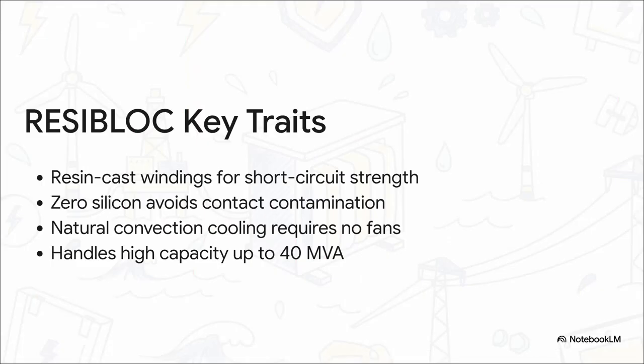Okay, let's pull all this together. Before this explainer, you might have just thought of a dry-type transformer as a generic category of equipment, but now you know the exact traits of a RESIBLOC specifically. You've got resin-cast windings for absolute mechanical short-circuit strength. You've got zero silicone construction to avoid contact contamination entirely, natural convection cooling with zero fans required, and, to top it all off, high-capacity handling up to 40 MVA without breaking a sweat.